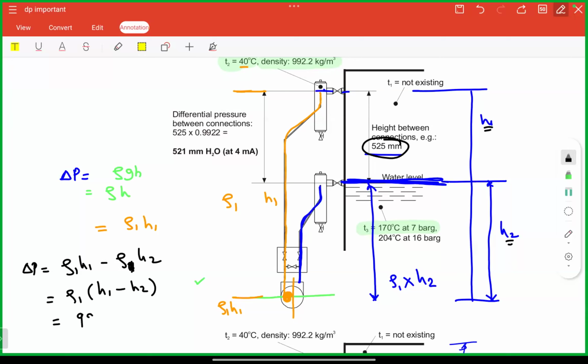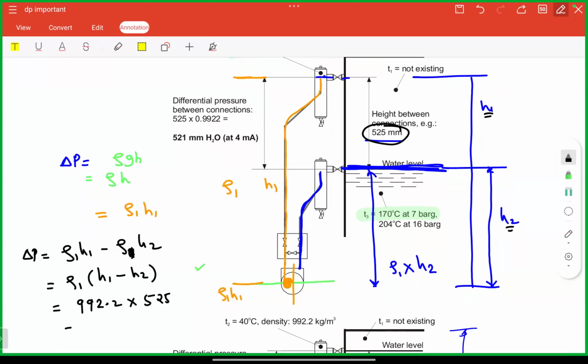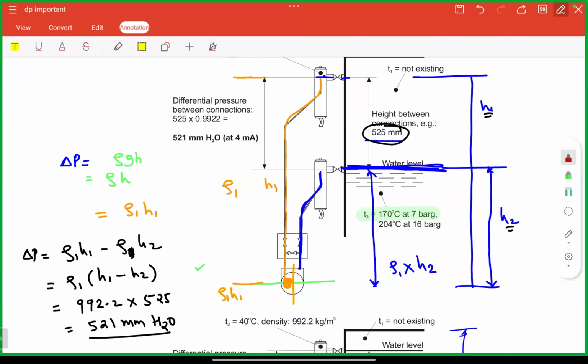What is the density? 992.2 into 525. तो कितना आएगा? 521 mm of water column. So you can convert into millibar, you can convert into PSI, whatever you want to do. But what is the differential pressure? When you get a differential pressure of 521 mm of water column, what should be the output signal your DP transmitter should produce? It should produce 4 milliampere.